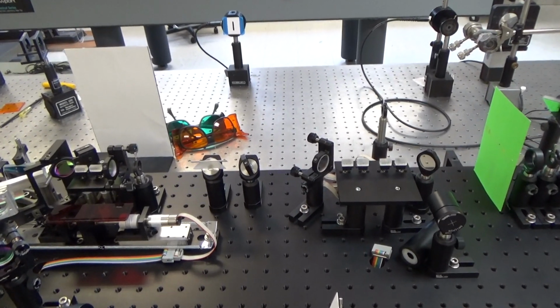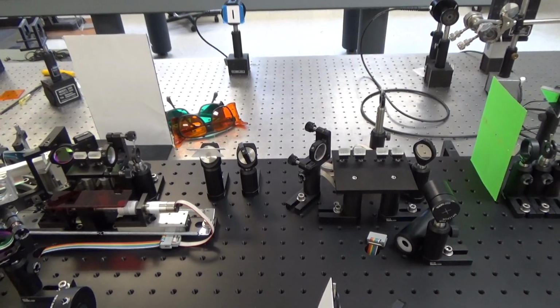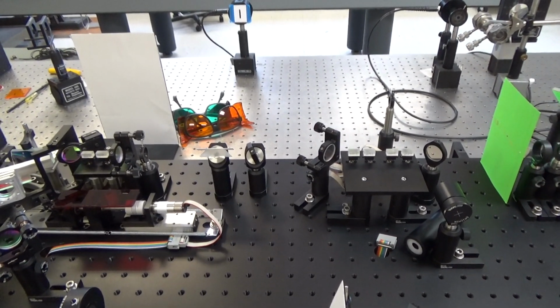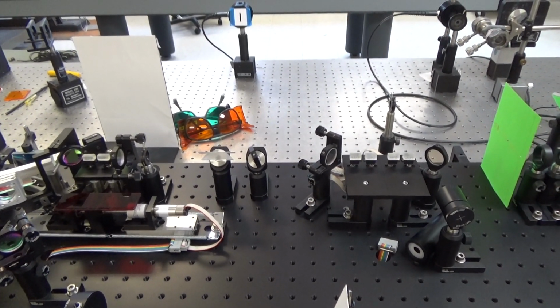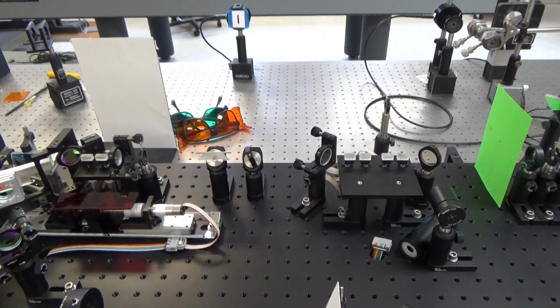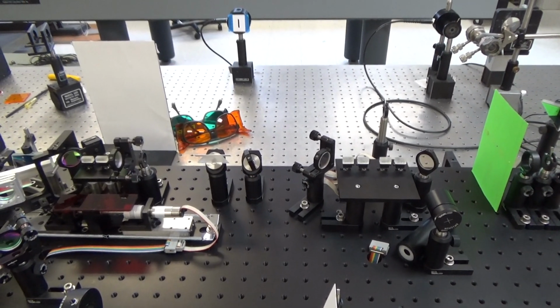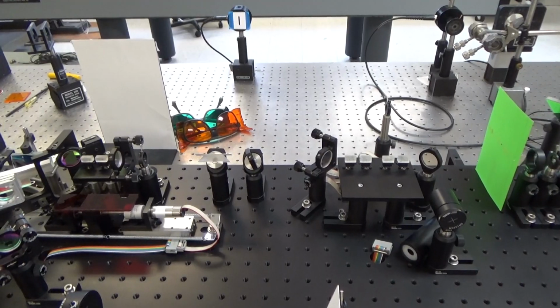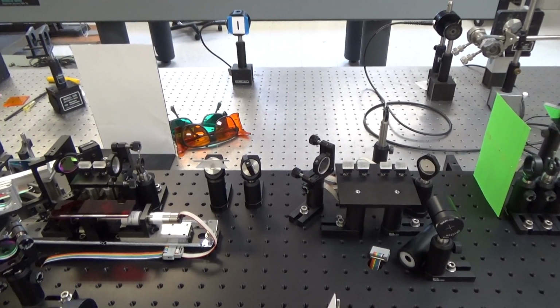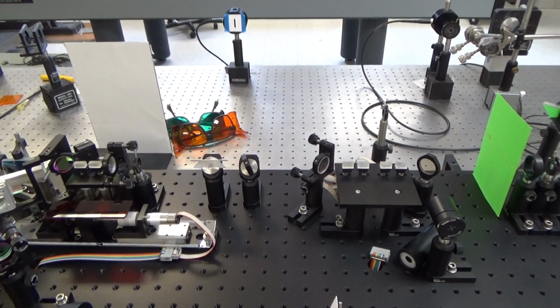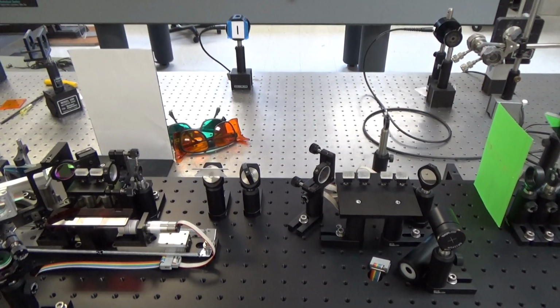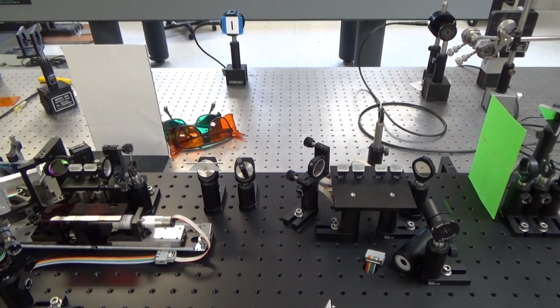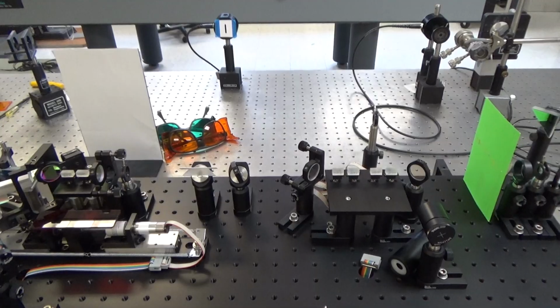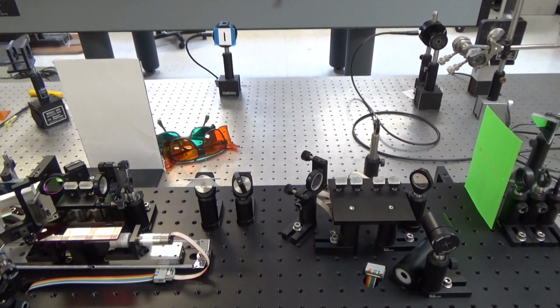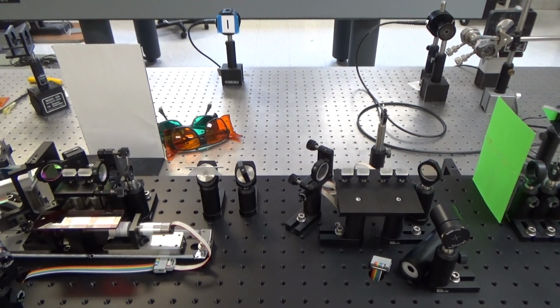The only reason to set the crystals to read 0 at normal incidence is to give you a reference point for the system. If you ever put crystals in or take them out, you can always find the normal incidence position. The program for the narrowband systems like this does not use the actual physical reading for the motor position. It's only mainly for your reference in the system.